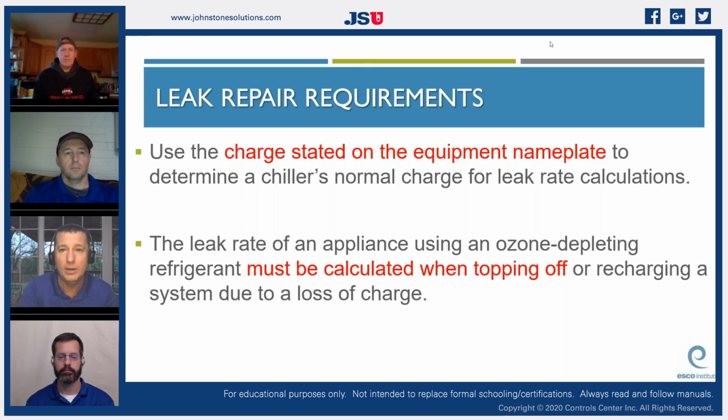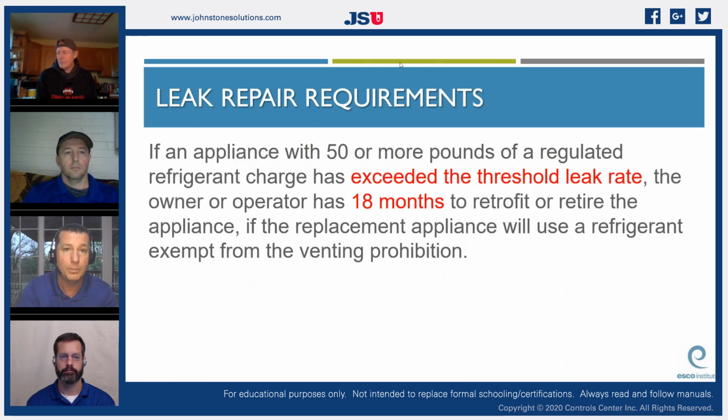So it's things to be aware of: you need to know what that total refrigerant charge is for a system. And if you're walking up on a piece of equipment and you don't know how much refrigerant is in that, don't start adding refrigerant until you find out how much refrigerant was originally in that system. Just so you have good, proper documentation. Because if you hit one of those leak rate thresholds, you are now repairing and you are documenting.